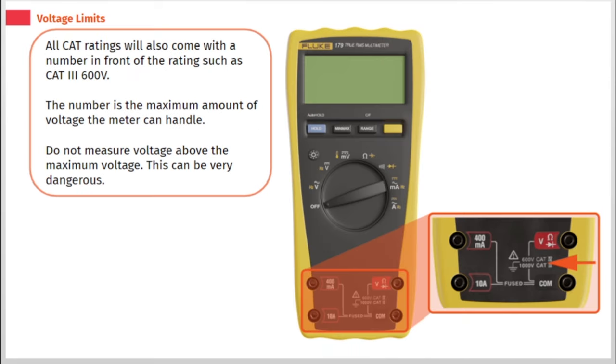All CAT ratings will also come with a number in front of the rating such as CAT 3 600 volt. The number is the maximum amount of voltage the meter can handle. Do not measure voltage above the maximum voltage. This can be very dangerous.